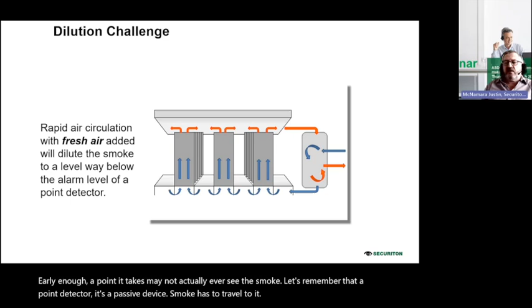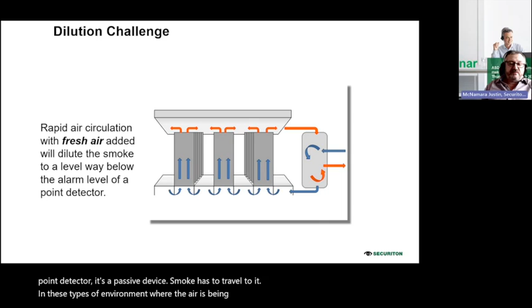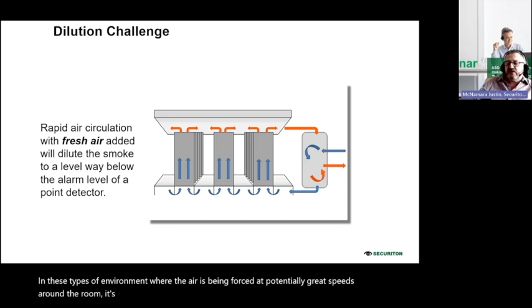A point detector may not actually ever see the smoke. Let's remember that a point detector is a passive device - smoke has to travel to it. In these types of environment, where the air is being forced at potentially great speeds around the room, it's possible that a point detector will not actually see the smoke at all.